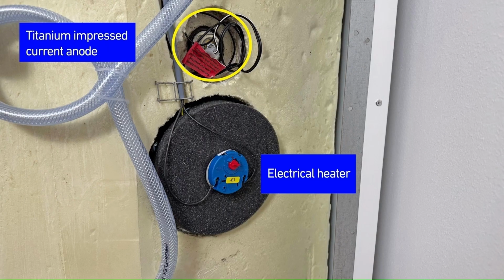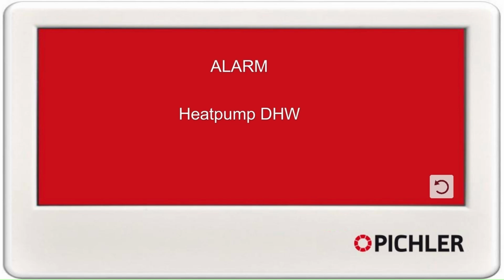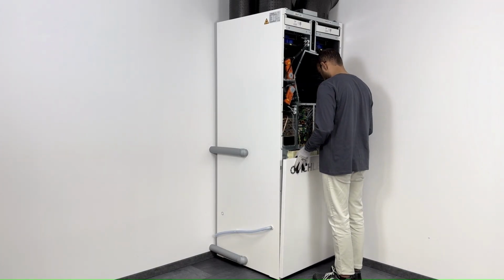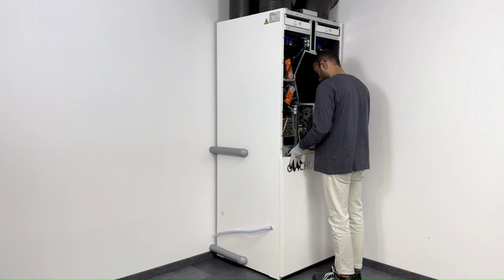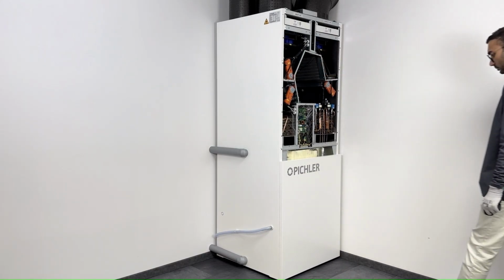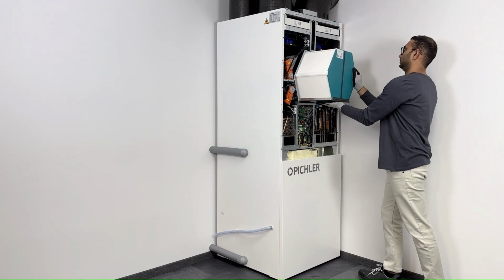The impressed current anode is maintenance-free. It is monitored electronically, and any deviation triggers a message in the PICHLER Connect app or on the screen of the control panel. Once you've inspected the anode, put the front hood of the domestic hot water tank back to its original position. Then reinsert the counterflow heat exchanger carefully.